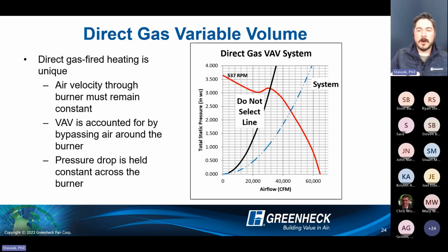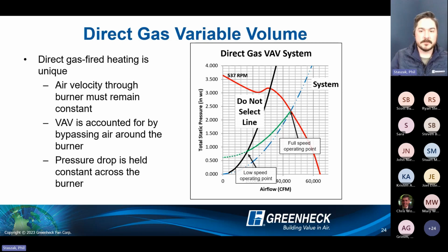Now, also with a direct gas fired system, this is a typical operating or system curve, that blue dashed line going all the way down to 0. It's unique with direct gas fired because there is that minimum pressure drop requirement for your burner section. 0.65 inches is required to properly and effectively burn the byproducts of combustion and allow for heat. So that 0.65 is actually a different operating point with direct gas fired systems.